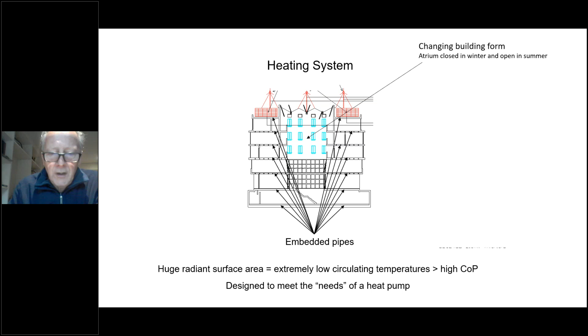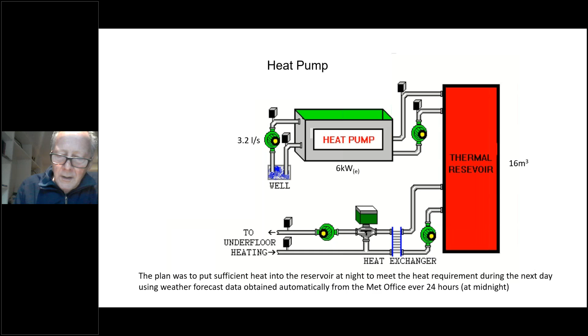The heat pump was designed with a thermal reservoir as shown in this diagram. The well was producing water at 3.2 liters per second, drawn from the top and returned in the bottom, with a 6 kilowatt electric heat pump, and with this large thermal reservoir. And the plan was to put sufficient heat into the reservoir at night to avail of the cheap night-rate electricity, and then to pull it from that reservoir during the day for the building. We needed the weather forecast to ensure that we weren't heating up the reservoir unnecessarily before warm weather and vice versa.